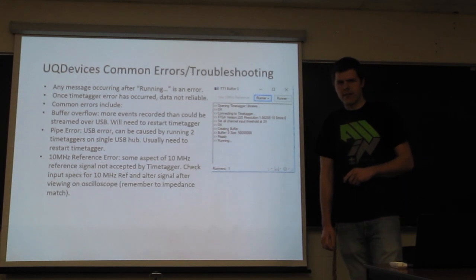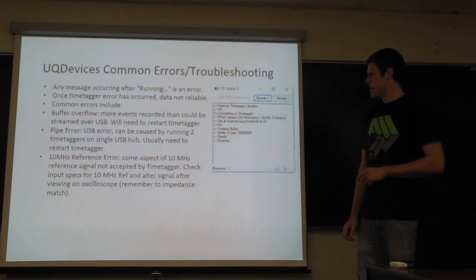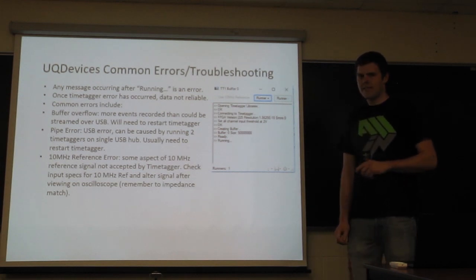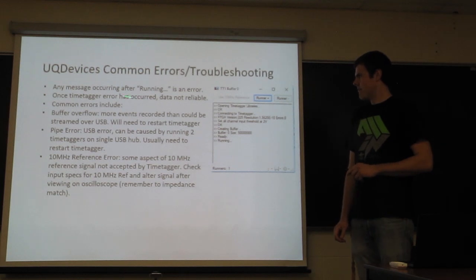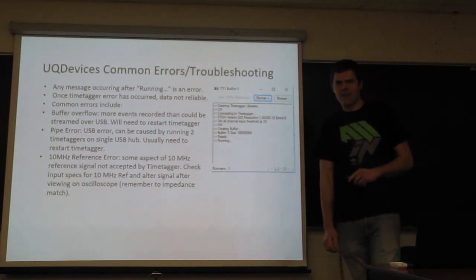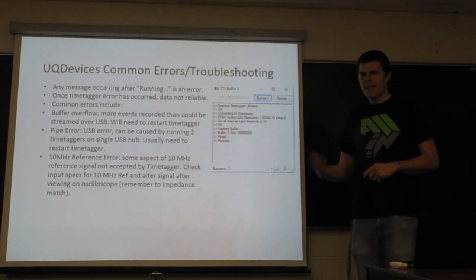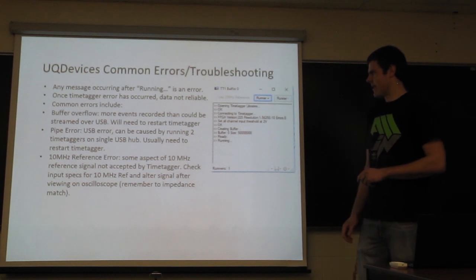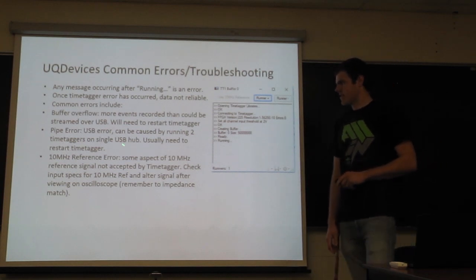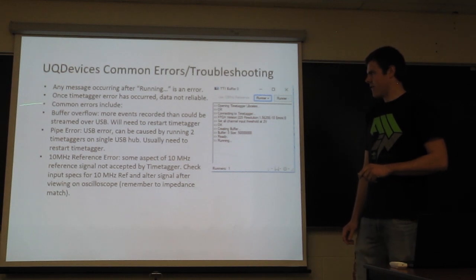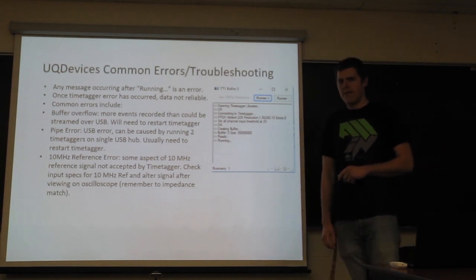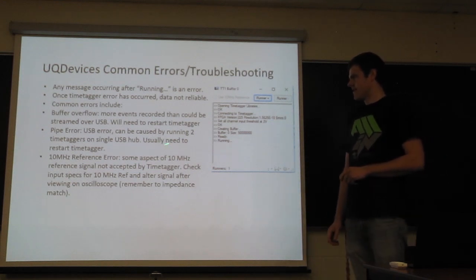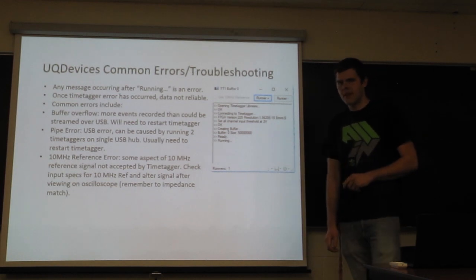So now let's talk about some common errors, some troubleshooting with this software. So again, I'll reiterate, if there's anything that happens after running, it's an error. And most of the time, if you see an error, the data afterwards is unreliable. The time tagger may keep going, but if you really want to trust the results, you need to stop and take care of it. So some common errors, a simple one, a buffer overflow, that's when you have too many events that go into the buffer before they can be streamed to the computer. This is simply fixed by restarting the time tagger and the software.